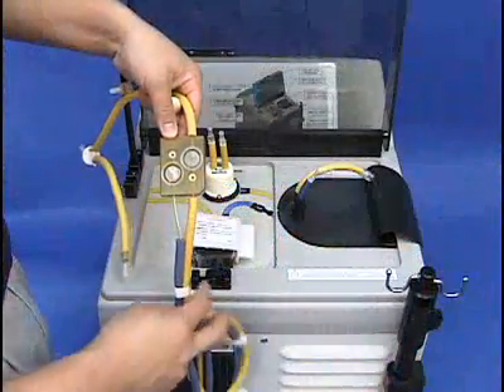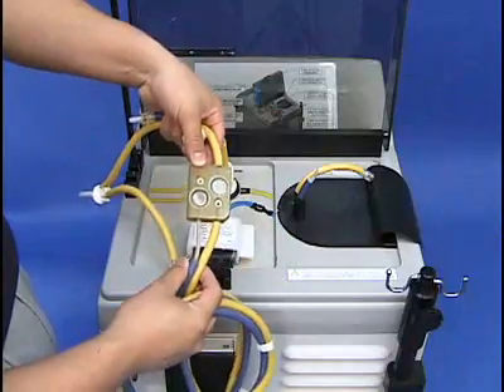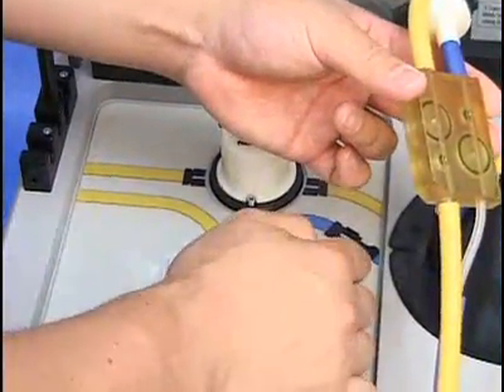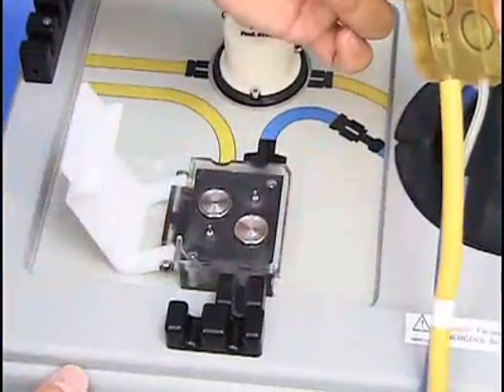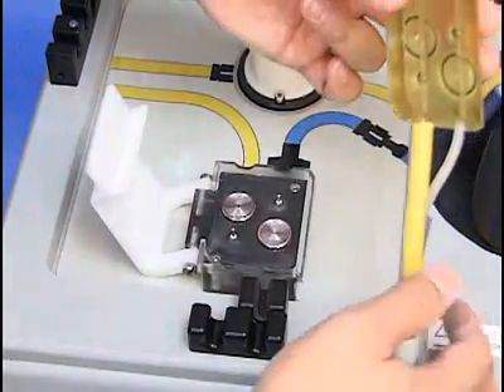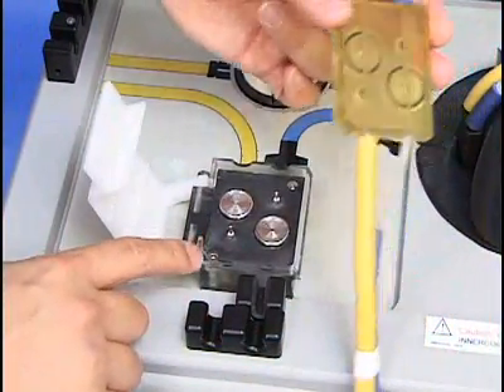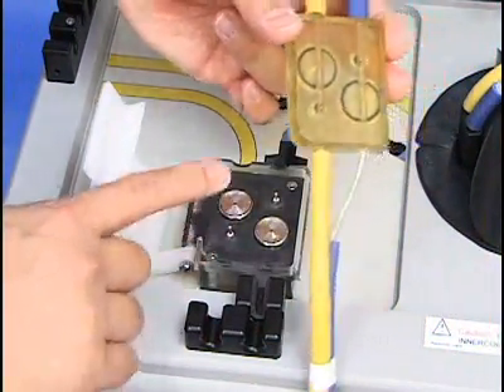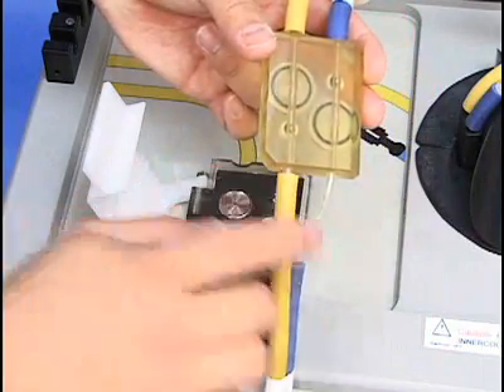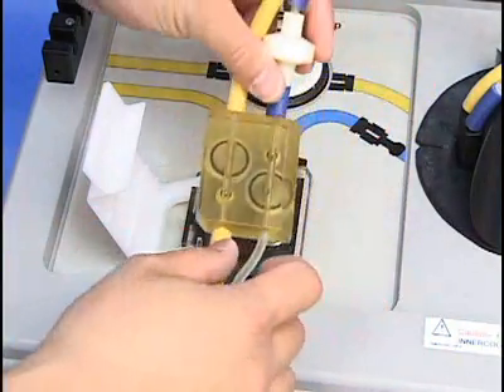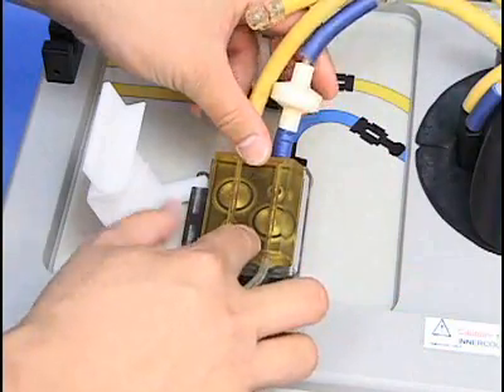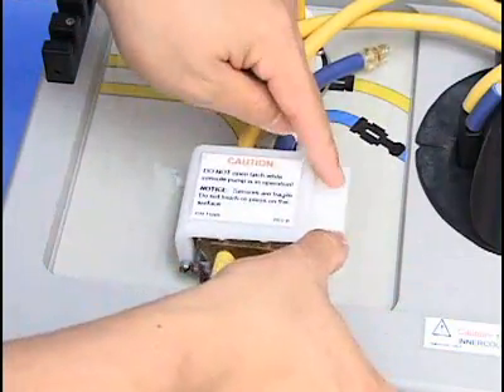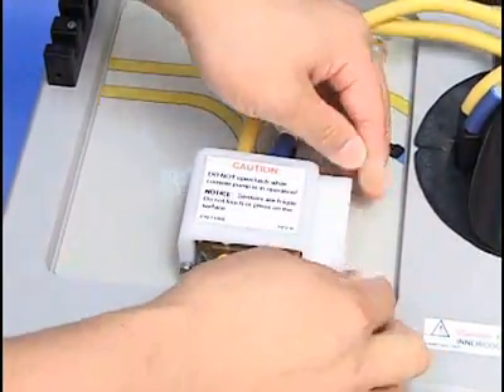Next, place the circulating set. First, mate the sensor block to the sensor housing, taking care not to touch the bottom of the sensor block or the sensor housing. Place the block so the angled edges are aligned. Then firmly close the latch over the sensor block. It should audibly click in place so that it will not easily move.